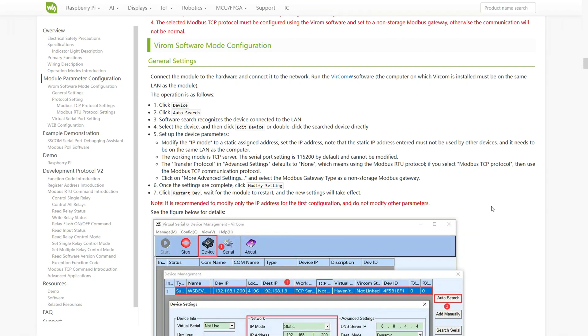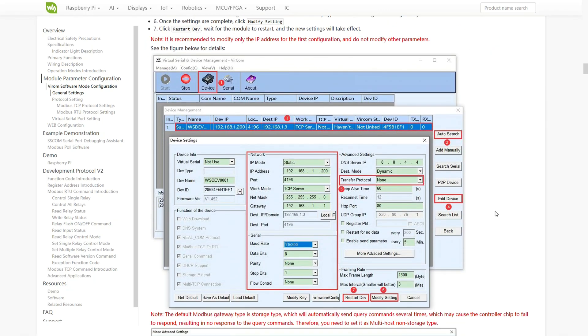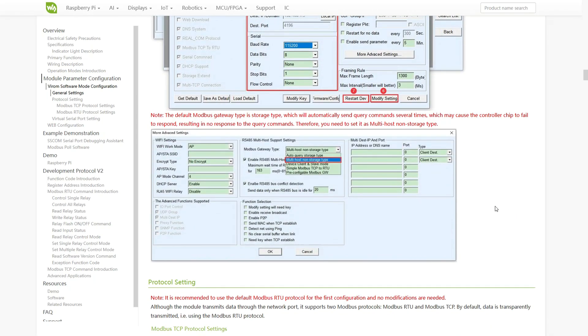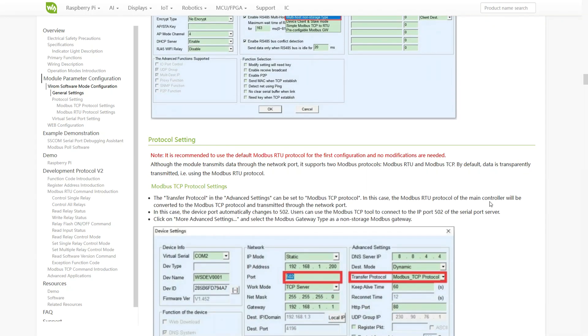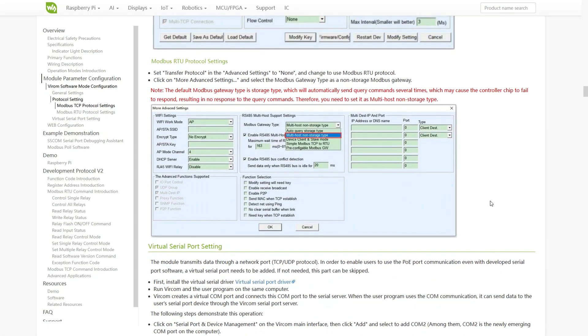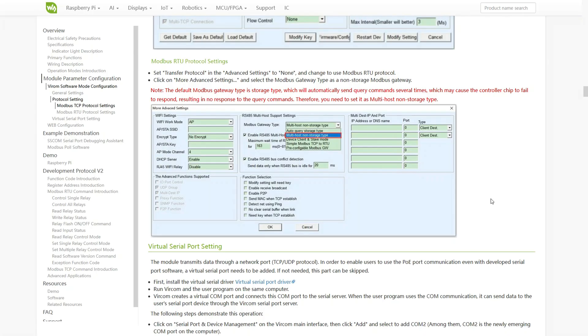VirCOM is a dedicated software from WaveShare designed for configuring and testing the Modbus PoE Ethernet relay module. It allows you to easily set device parameters such as IP address, operating mode TCP server, communication protocol Modbus RTU or TCP and Modbus gateway type. The recommended type is non-storage. The software also lets you apply and activate new settings on the device, making configuration straightforward and user-friendly.